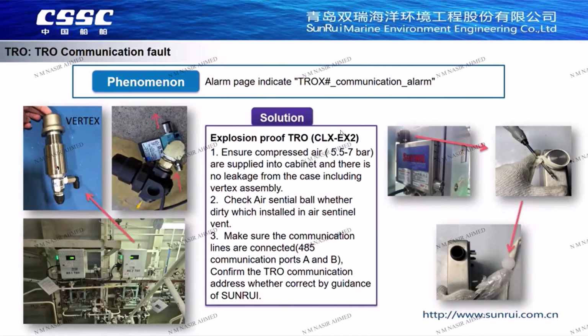For the explosion-proof type of TRO, type CLX-EX2, an air sentinel is installed to maintain constant air pressure in the TRO box to achieve explosion protection, so it is also necessary to check that the air pressure is sufficient. The air solenoid valve can be checked. If the valve is normal, check whether the cabinet is well sealed. Make sure there is no air leakage around the TRO box. If the air supply is confirmed to be normal, check whether the small ball in the ventilation cap of the air sentinel is dirty or stuck. Generally, reinstalling after cleaning can solve this problem.